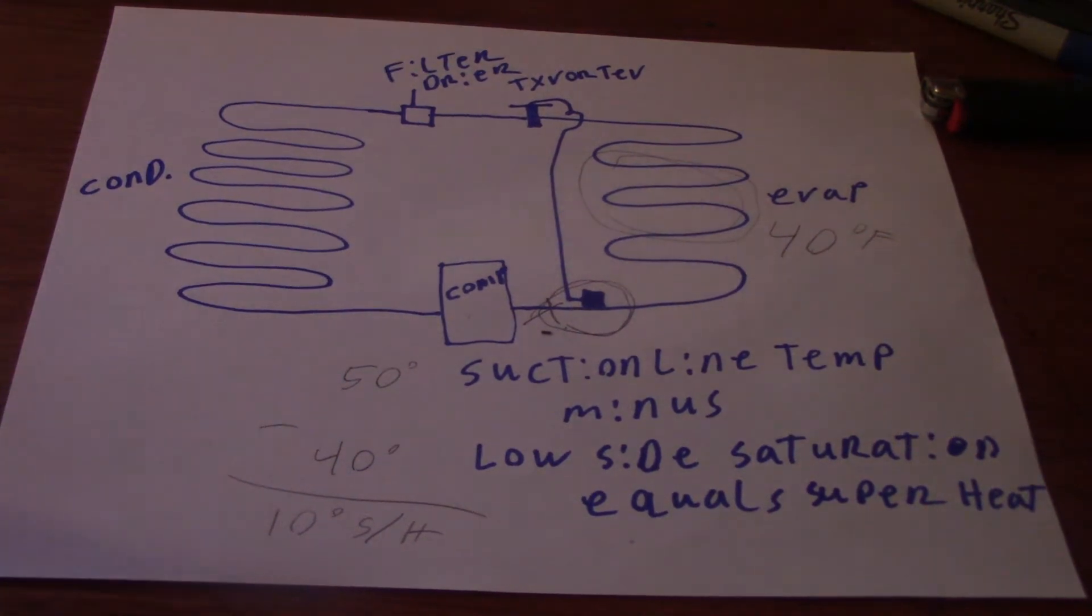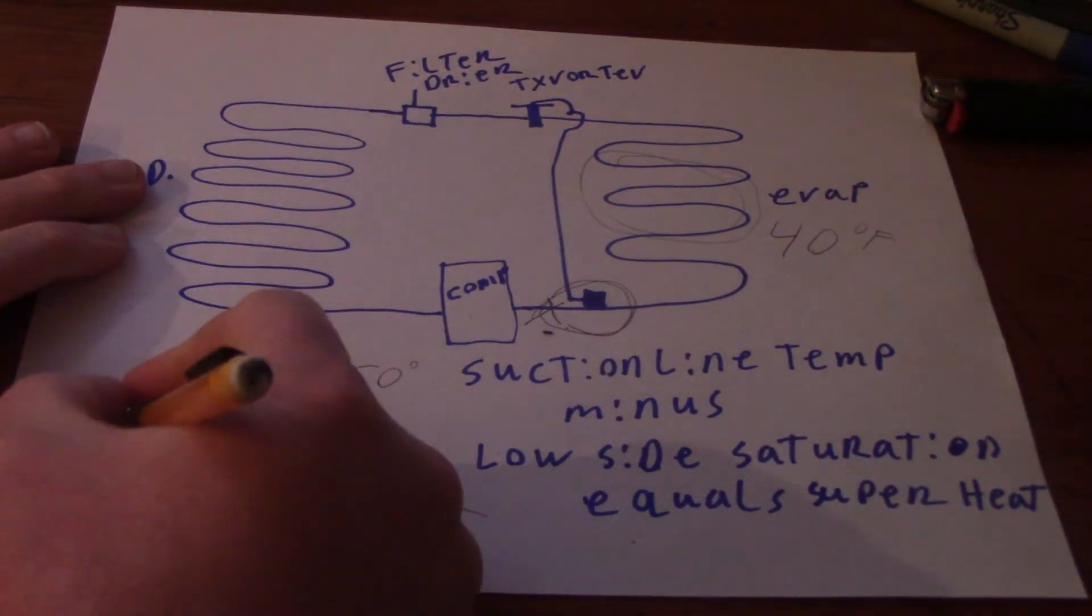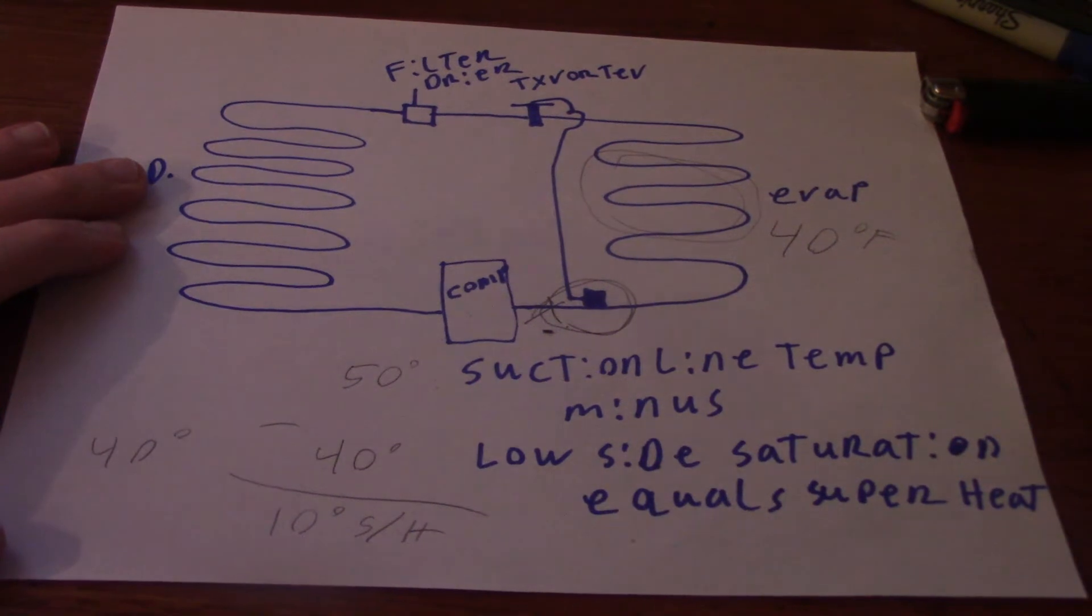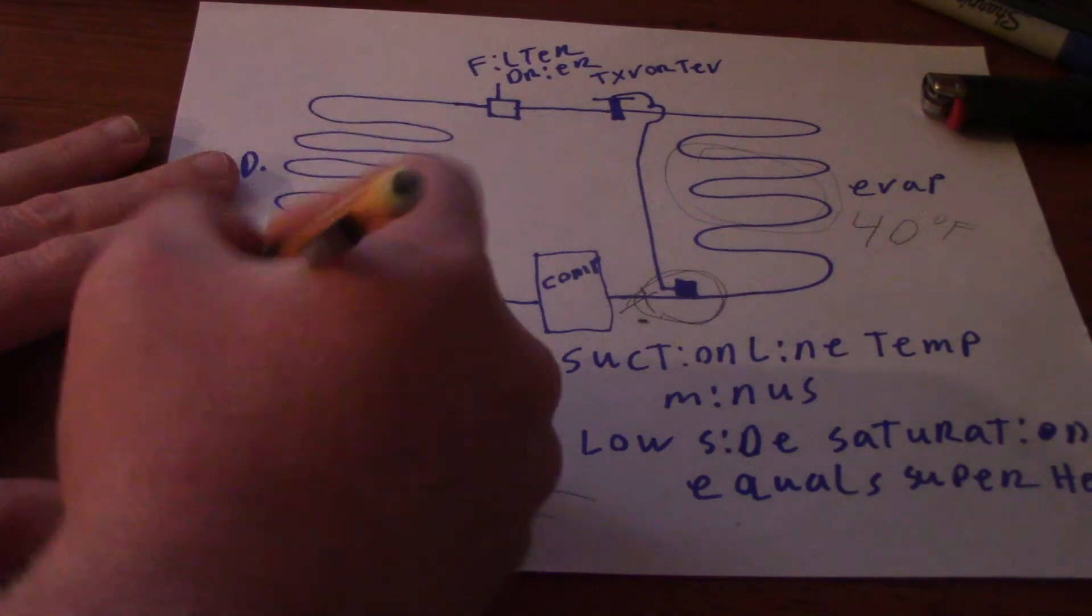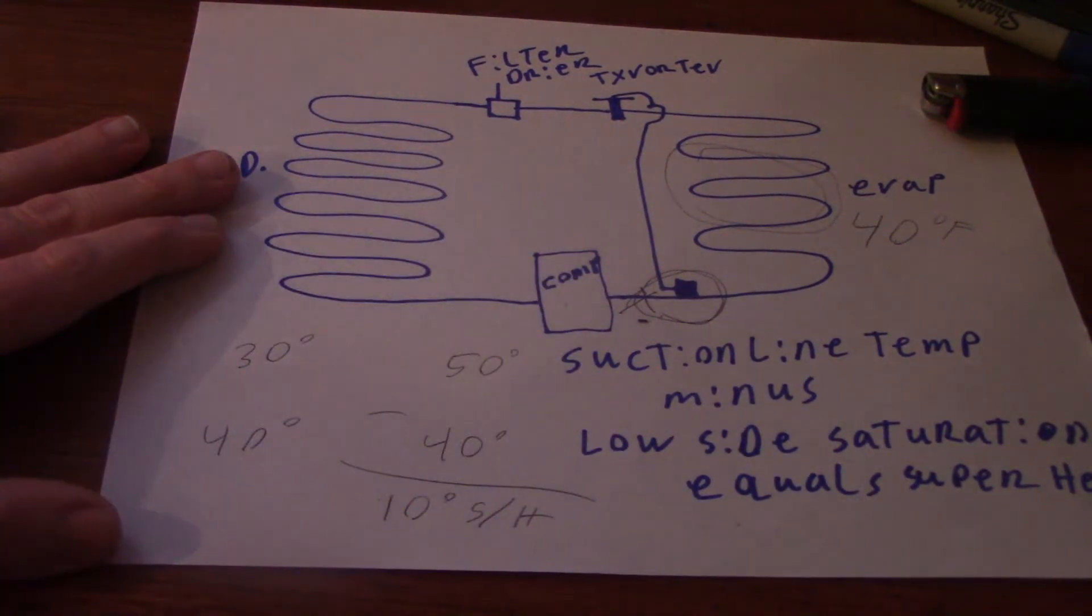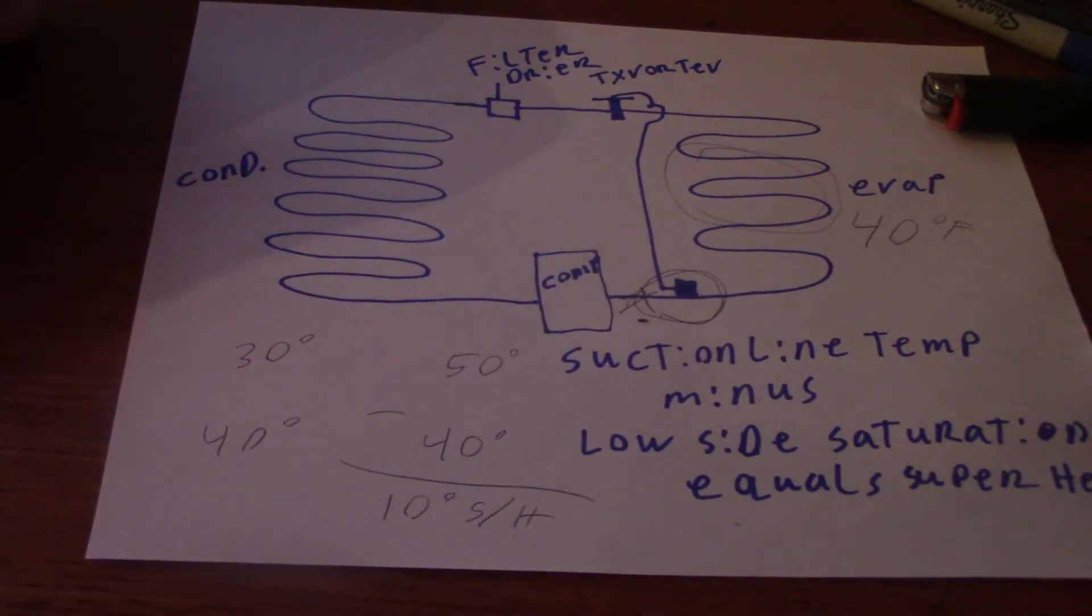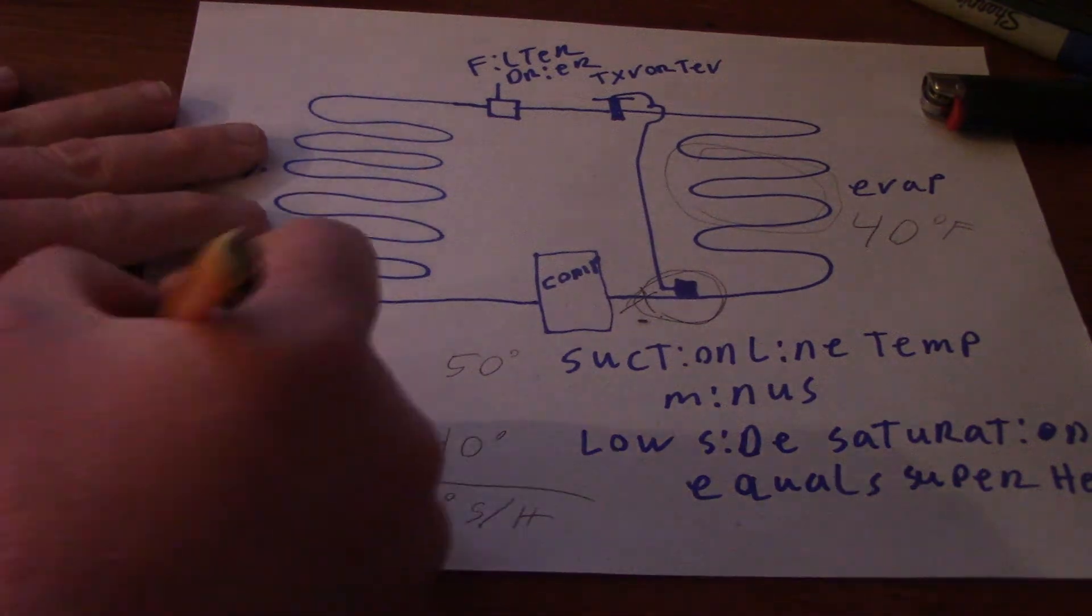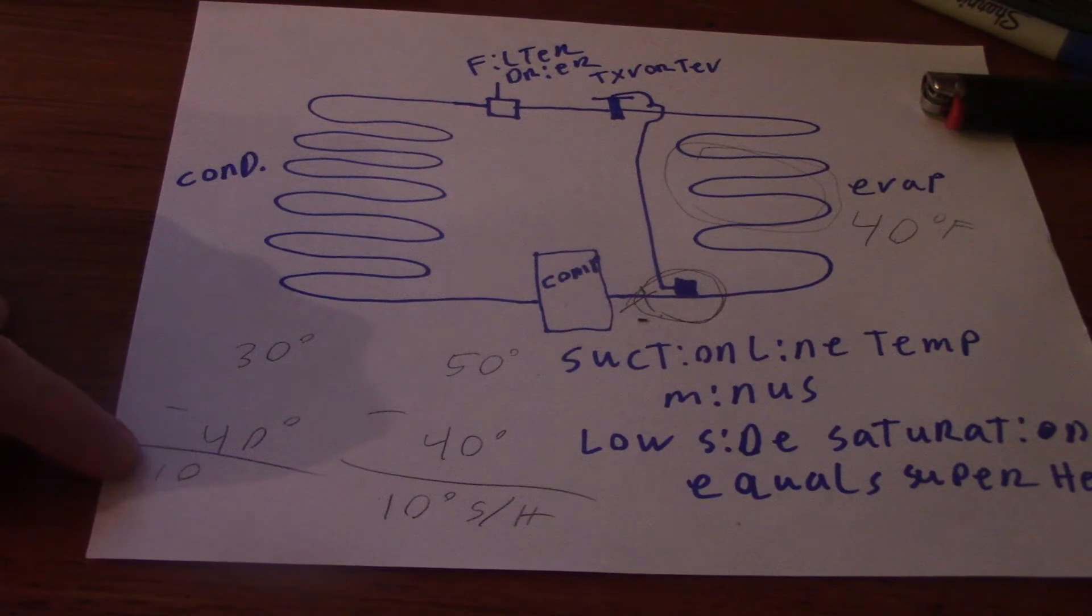If you had it backwards, let's say the system was a piston that was grossly overcharged. Where you had saturation of 40, so we're going to make a new 40 right over there, but your suction line let's say ended up being 30 degrees.